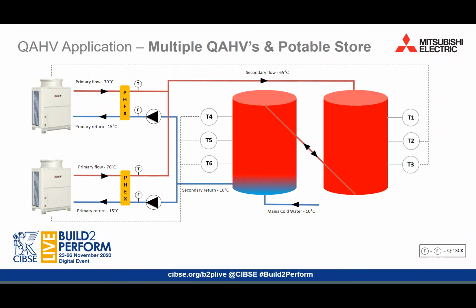When using 2 or more QAHVs, the preferred control method is to control the temperature in the vessels via 6 temperature sensors located in sensor pockets at the top, middle, and bottom of the first and last vessel. The unit can then be commissioned to control the vessel temperature according to the target set point at any of these 6 positions. Here, for example, let's say again we're targeting a set point of 65 degrees Celsius. The user may choose to turn the QAHV off when sensor T5 reads 65 degrees or more, and then turn the unit back on when sensor T4 reads 60 degrees or less, therefore assuming that the first vessel in the series is full of hot water. Again, the system can be commissioned to operate in 3 control modes, each with different on-off conditions. And it should be noted that up to 16 units can be controlled in a single control group.